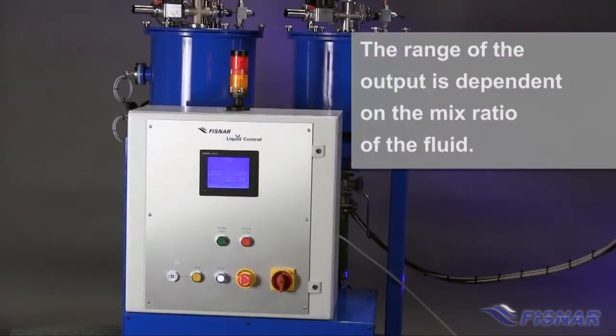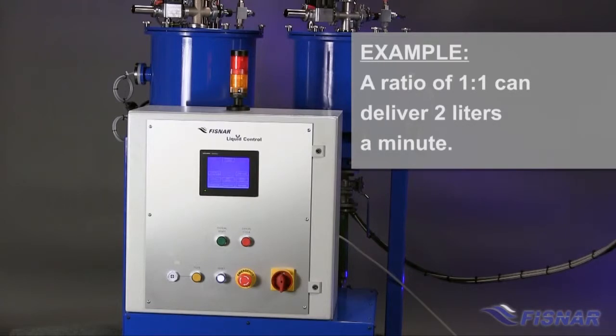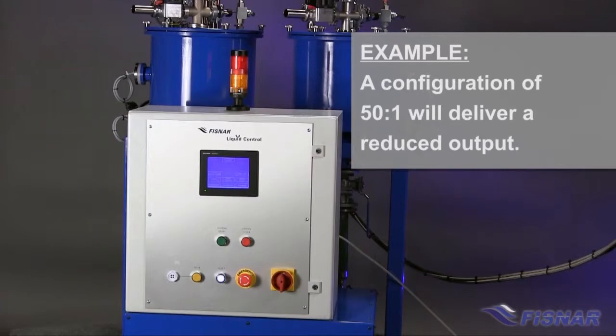The adjustment in range of the output is dependent upon the mix ratio of the fluid to be dispensed. As an example, a ratio of 1 to 1 can deliver 2 liters a minute, but a configuration of 50 to 1, which is the maximum ratio that the machine can accommodate, will deliver a reduced output.